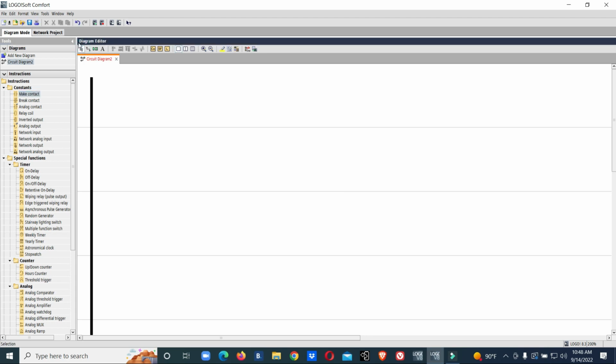I'm Senappa. In this video we will see how we can configure the PID controller blocks in ladder logic. The scenario is, we have one analog input, and based on this analog input we will control a pump VFD. This analog input is coming from a pressure transducer which measures 0 to 10 bar. We will maintain 4 bar, so we have to control the speed of the VFD to maintain that pressure. So we will make logic for that.